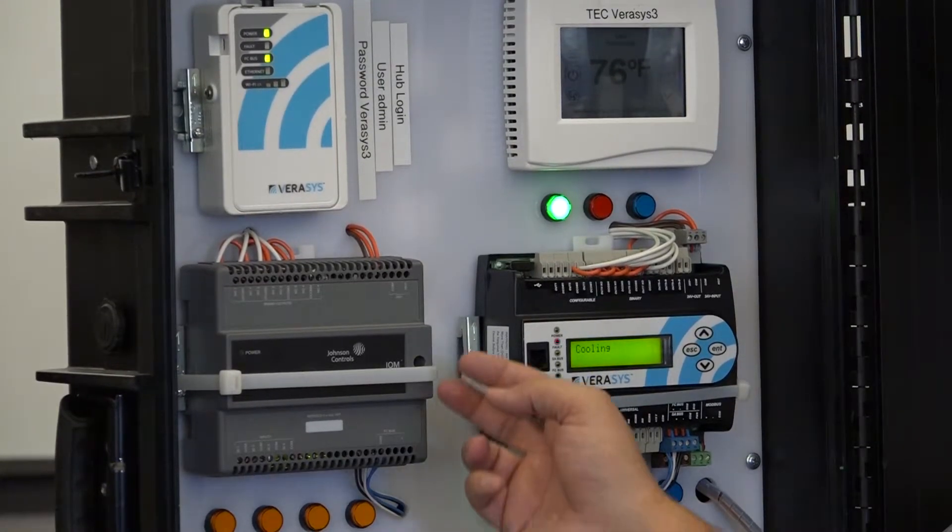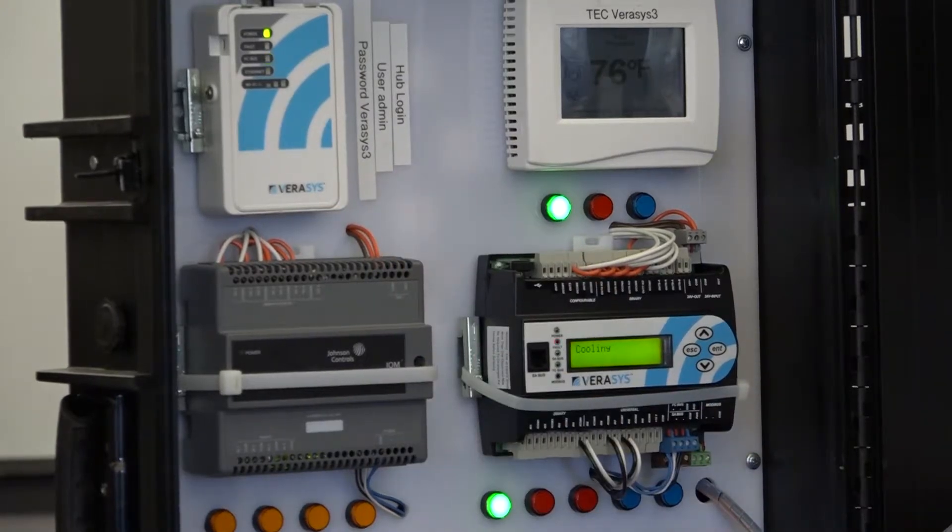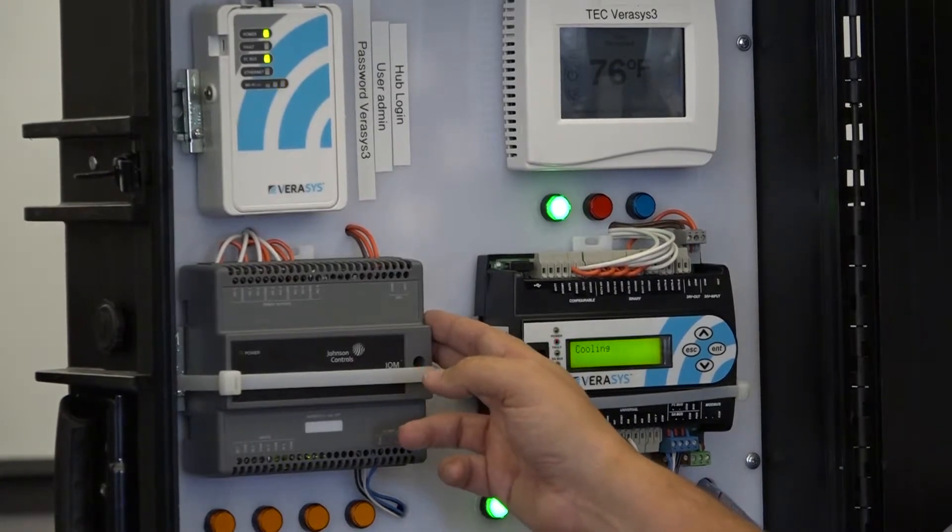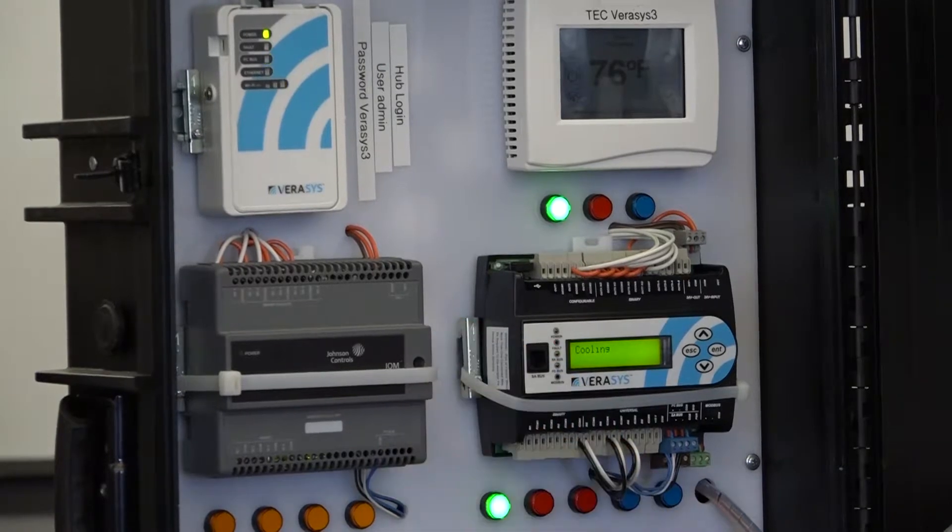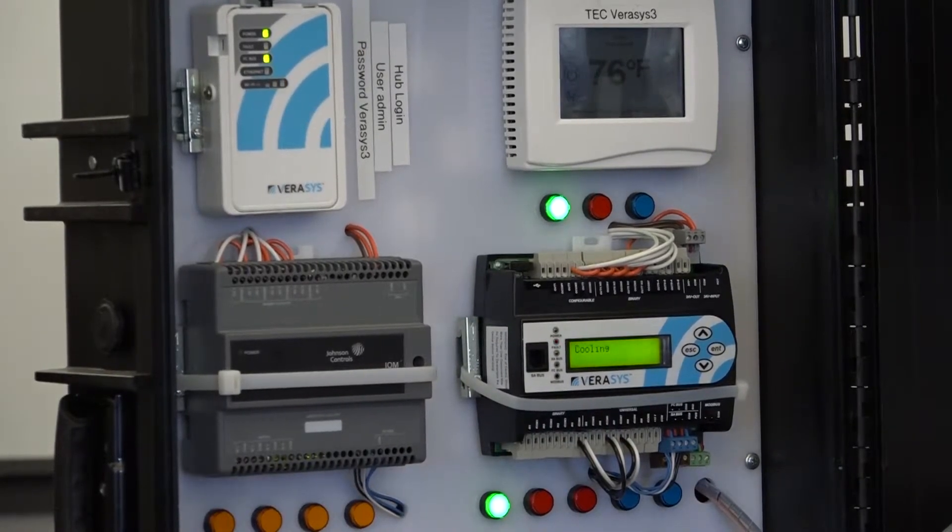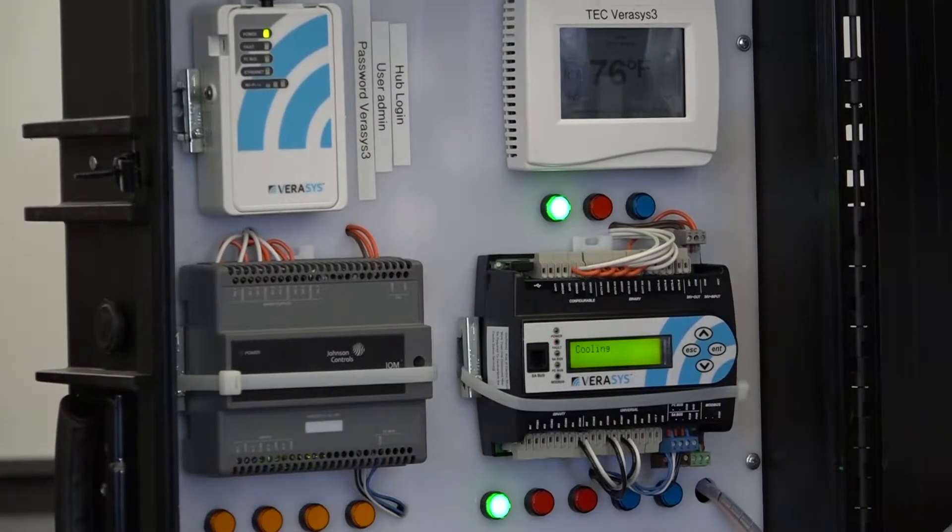In addition to interlocks, there are features on the smart building hub called load shed and global shutdown. These require an IOM100 installed. Load shed takes one of the binary inputs, and if it makes, it will initiate load shed across the Verasys system.